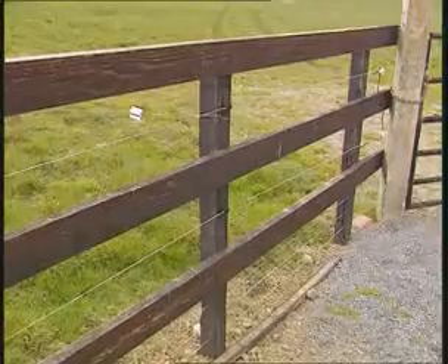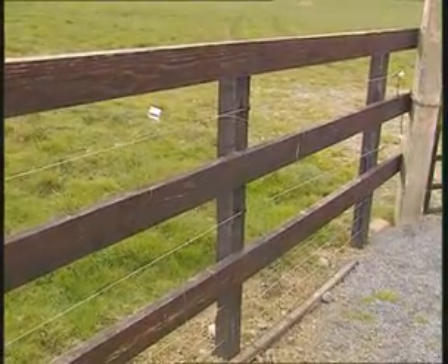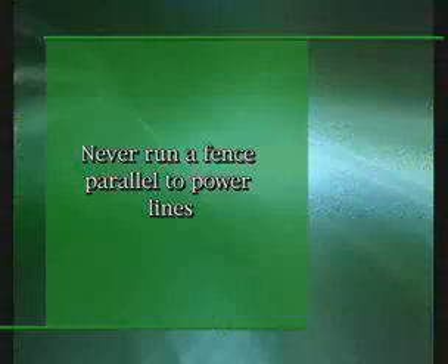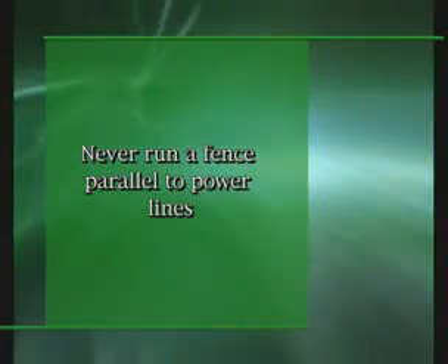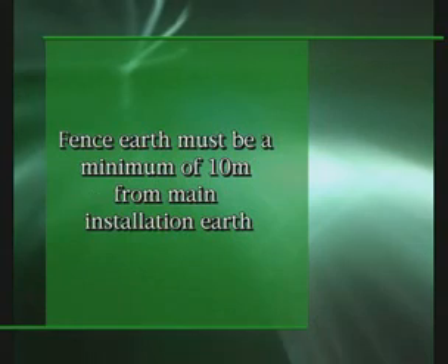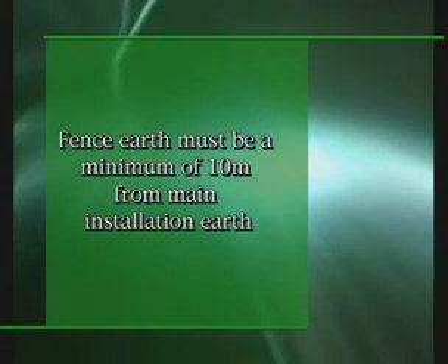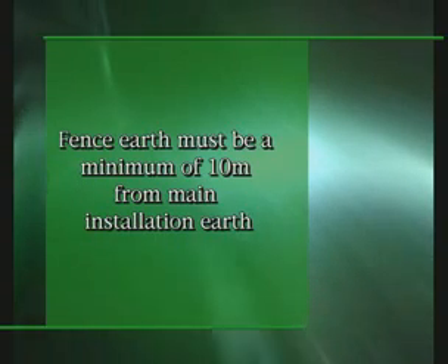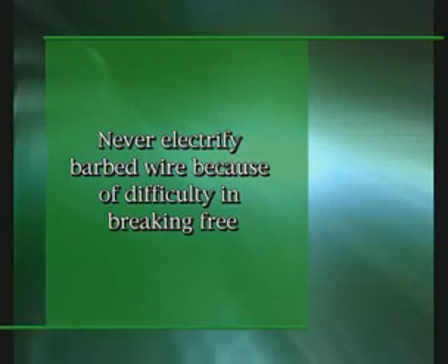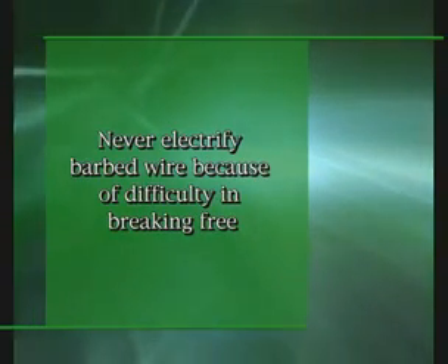Should not be mounted on ESB networks or telephone poles. Must have a minimum degree of IP54 electrical protection if located outdoors. Never run a fence parallel to power lines. Fence earth must be a minimum of 10 metres from main installation earth. Never electrify barbed wire because of difficulty in breaking free.